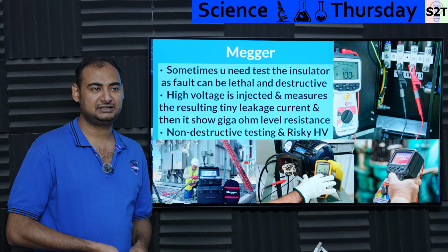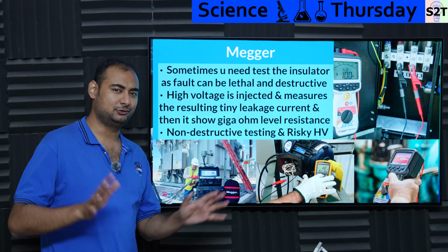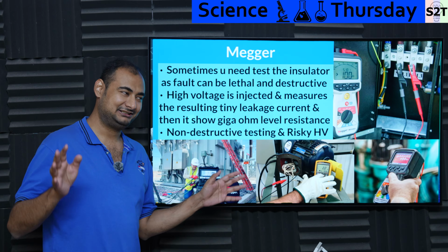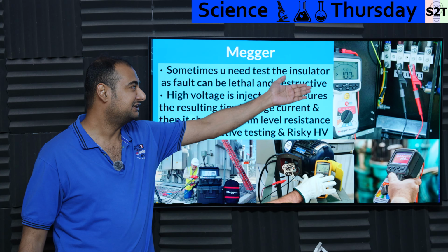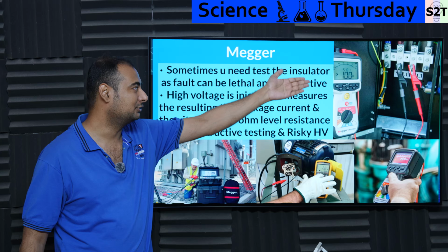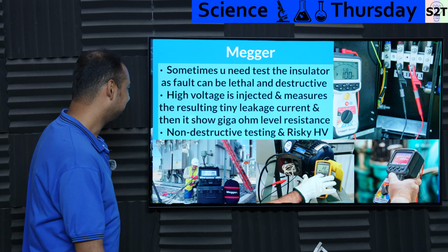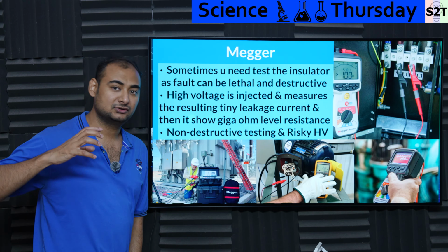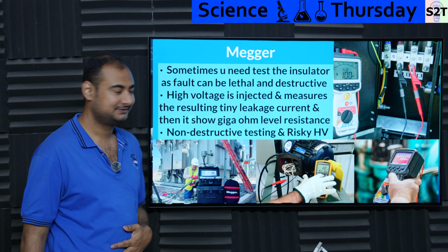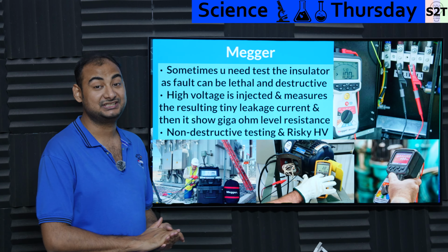They can start with mild voltage of 500 volts and go up to kilovolts. I don't even want to know what kind of oomph they're putting for 100 gigaohm. Fundamentally, they are pushing a lot of voltage and measuring the leakage current, and that's how they show you a gigaohm level system.